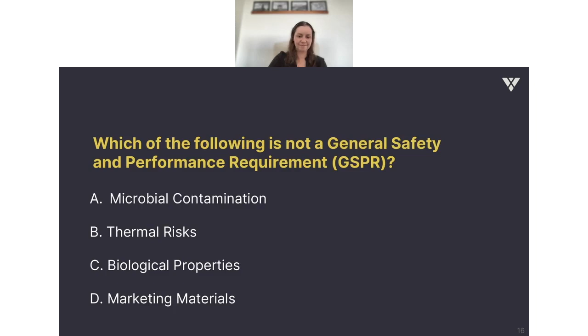So in your regulatory requirements then, what are the potential gaps? If you already have US clearance or approval, you probably have a lot of the things that you need, but we don't want to say that everything is very easy and you can just use your FDA file, because that's not the case. The general safety and performance requirements, which I've already highlighted, are going to be the main area where you have to go back and really look carefully and look at which standards you might have to get up to speed with to comply with those.